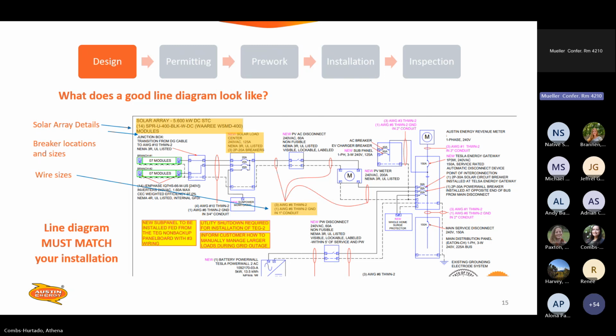So what does a good line diagram look like? This is one example. There are lots of different ways to have a good line diagram. This is one of them. It's got all your components called out. It's got your number of modules. It's got some amp ratings of your inverters. It's got wire sizes. It's got conduit. It's got pretty much everything that you're going to see on site. Notice that you go solar, disconnect, meter, interconnection. It's always going to be that way. So yeah, this is chock full of information. It's clear to read, and it's got all the information you need. So yeah, do something like this.